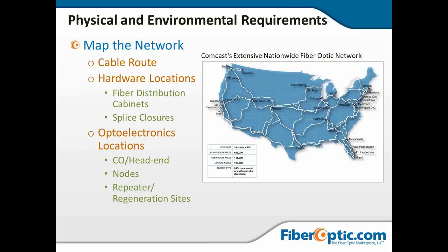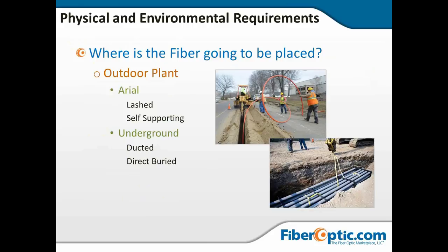Where will the fiber be placed? Aerial — either lashed or self-supporting — or underground cable? Will we use a single inner duct or a duct bank of rigid PVC between manholes? Or direct buried? Direct buried is the least favorable option — too much potential for disaster, no protection for the cable. You need to spend the extra money to get armored cable. All of these options must be offset against cost.